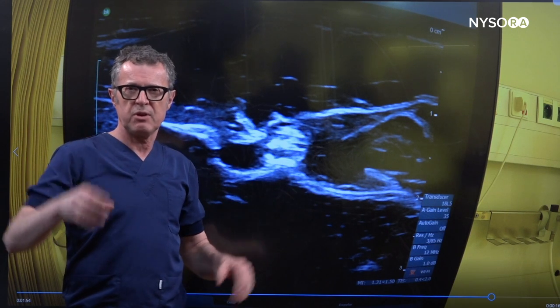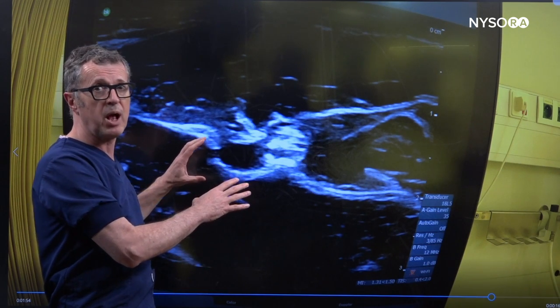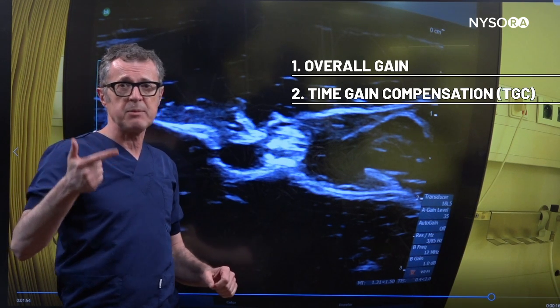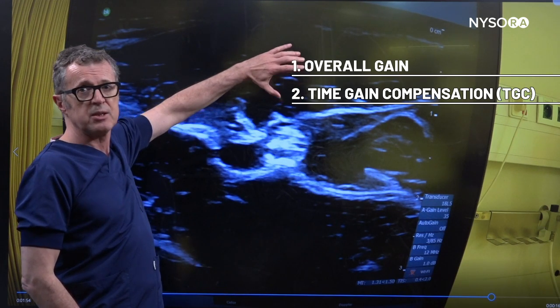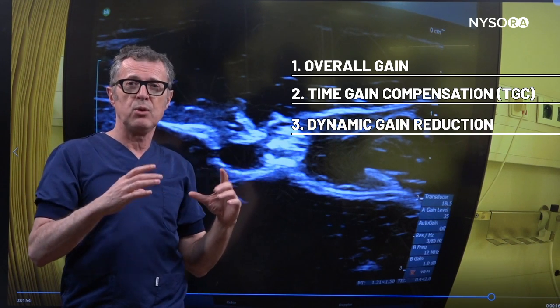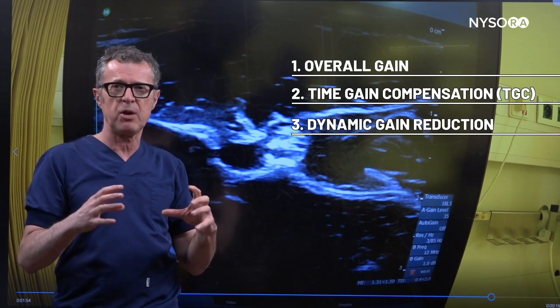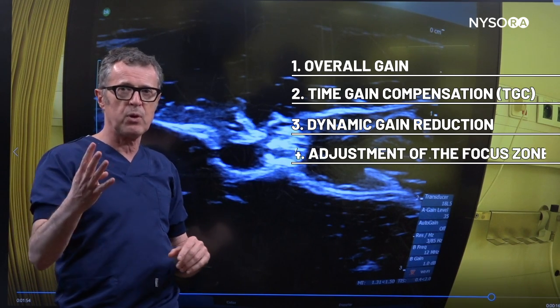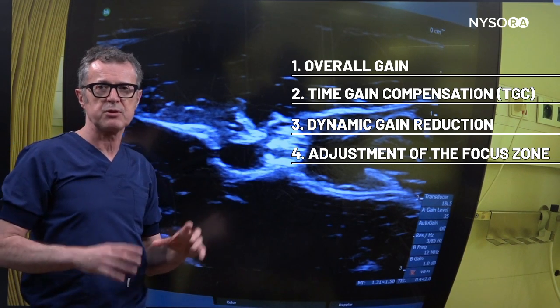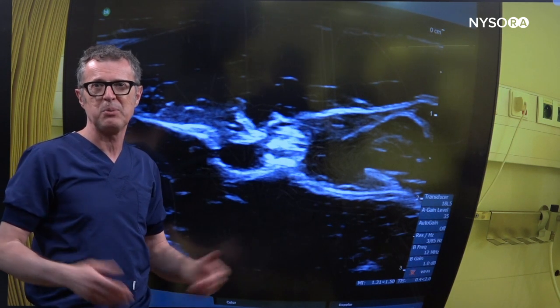In summary, we demonstrated four simple ultrasound machine adjustments to get the best possible image for the median nerve block: first, we adjusted overall gain; second, we adjusted time gain compensation to de-emphasize structures above and below the nerve; third, we used dynamic range and reduced it to accentuate the fascia sheets — as the image gets more compressed it becomes edgier and sharper for fascia recognition; and fourth, we adjusted the focus point to the level of the anatomical structures of interest. Make sure you press the subscribe button and never miss the beat as more videos will be coming soon.